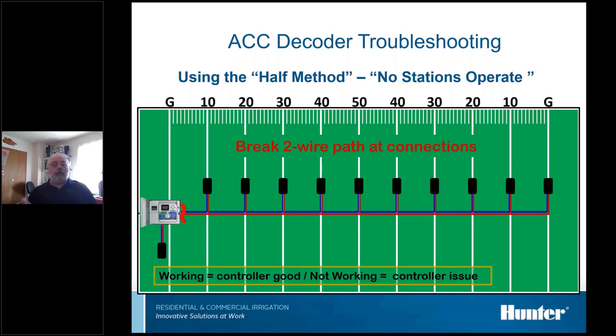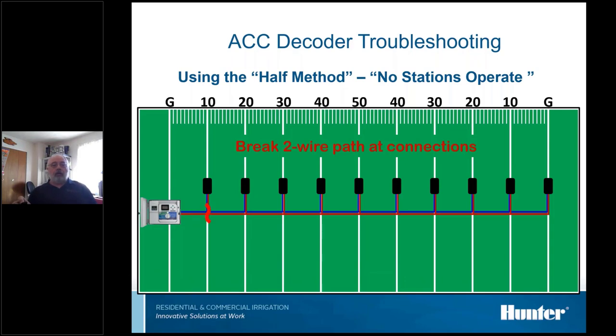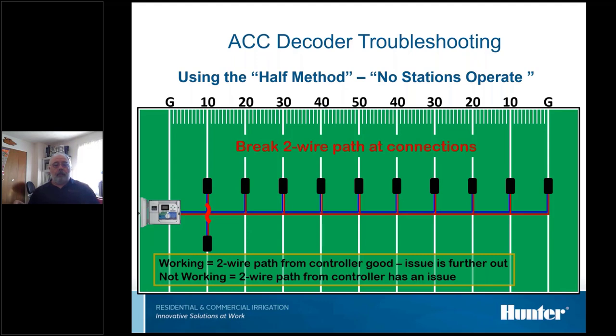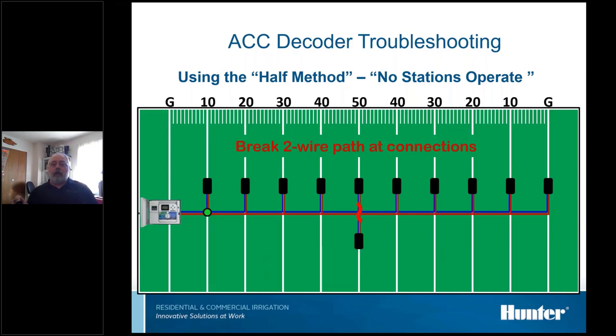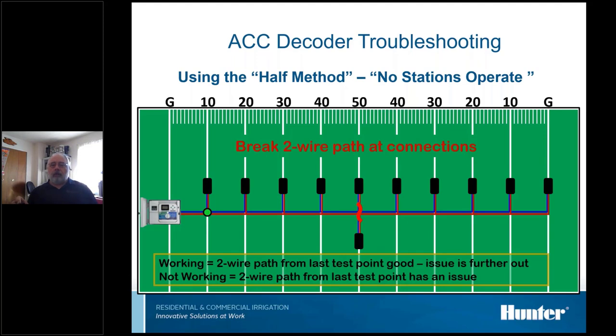If you can, we know the controller is good, then that says we definitely have a problem out in the field. Then we always go to the first location and check there first. It's not necessarily, it's a good habit. We find problems right there often enough that it's worthwhile doing. And then from there, once we prove that that's okay, we're going to go halfway or about halfway out and check. We're going to literally disconnect the wire, see what happens.